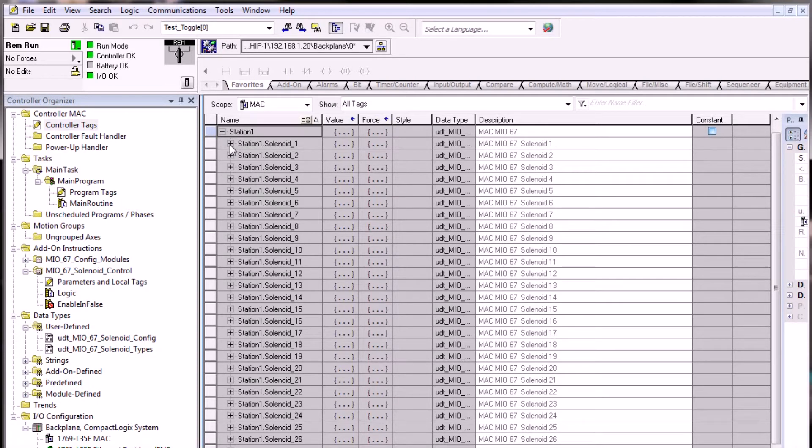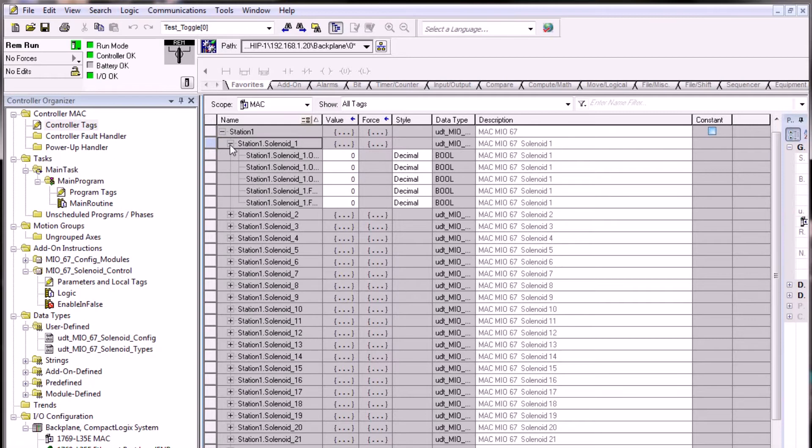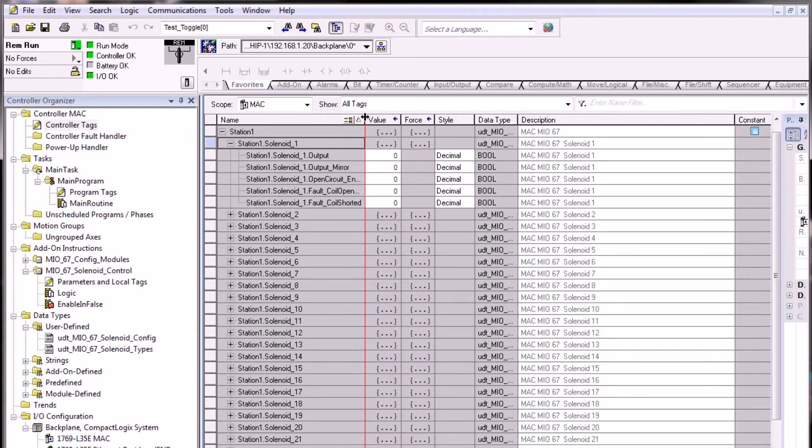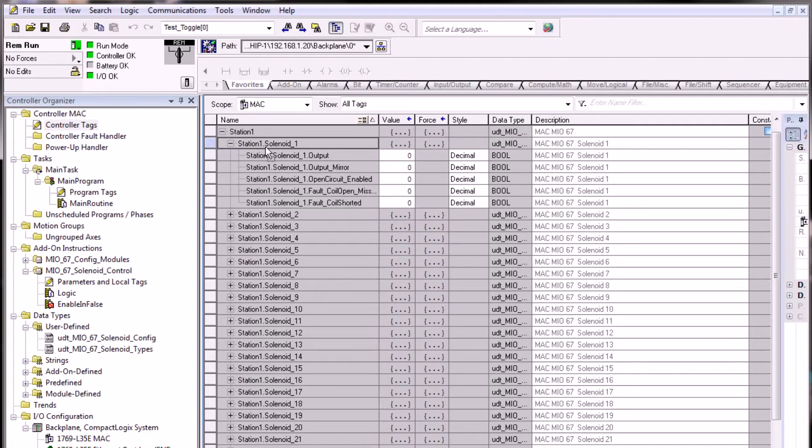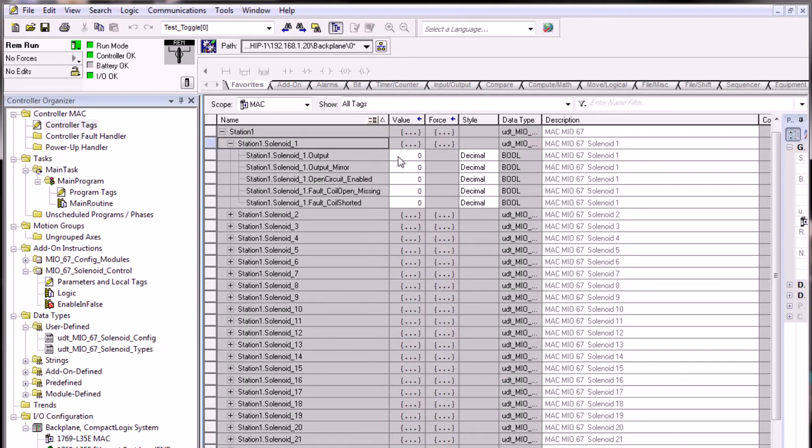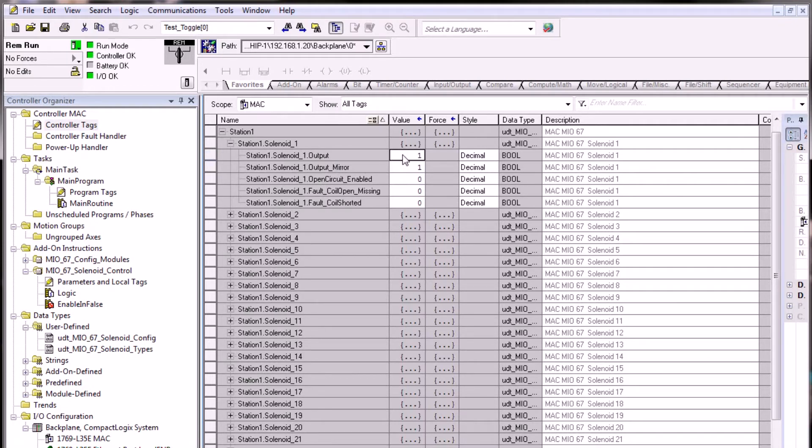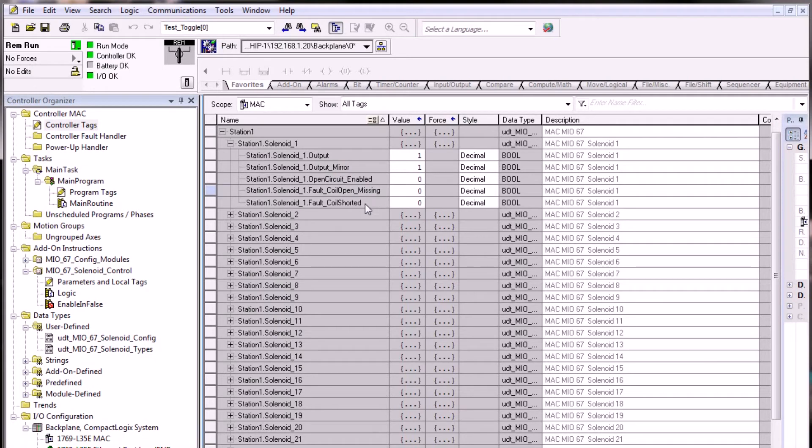In order to turn on the solenoid first for station 1, we will need to reference it here in this tag. Since we have no ladder logic, we can go ahead and expand this option and see the structure that is inside station 1.solenoid 1. Here we can see that there are five different types of options they can either be input or output. In this particular case, in order to turn the solenoid output on, we'll want to put a 1 into the output status. We'll notice that the valve does respond by turning the solenoid 1 output on and then also confirms by turning on a status bit to confirm that the output has been mirrored. We'll also notice that there are fault indicators depending on how the valve stack is configured. For instance, if there is a valve short, this particular valve fault coil short will be a 1 if there is a problem with the valve if we try to turn the output on.